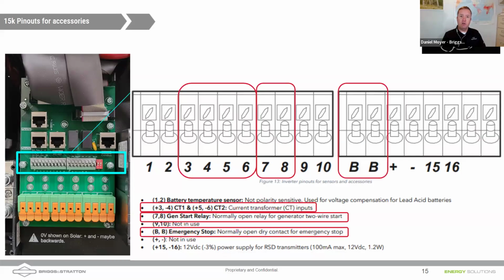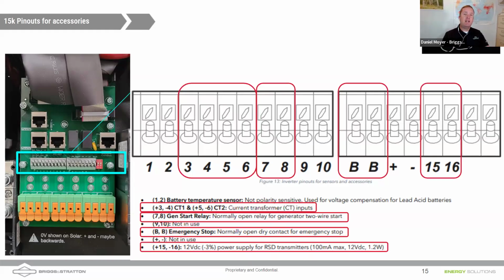E-stop, right? A lot of codes and jurisdictions are requiring emergency stop buttons. You hit this red button, the mushroom button that you're going to install in a readily accessible location. It's going to stop all power coming in and out of the Sol-Ark. It's also going to stop powering the transmitter for the rapid shutdown power supply inside of the Sol-Ark, so that any Tigos or AP Smart System rapid shutdown devices will also shut down the solar as well. And that's where we're down there on pins 15 and 16. Now, Andrew, some of the criticism, and not criticism, but just feedback, is that that transmitter, the power supply on that pinout, is 100 milliamps.